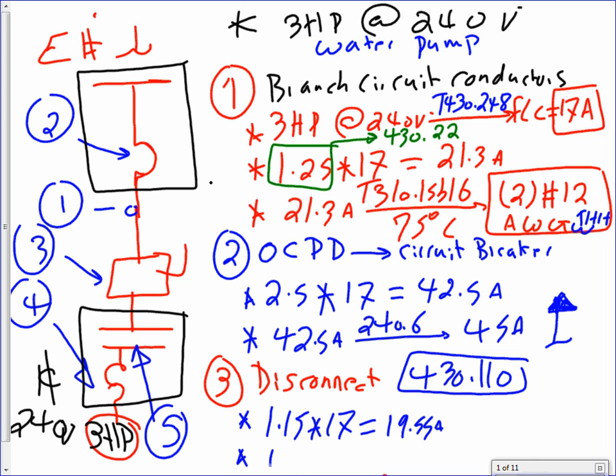If you take the 19.55 amps, you're going to take this one to the DeWalt, page 3-12. You're going to get 30 amps. Gentlemen, when you say DeWalt, page 3-12, that's what I told you. On the test, if you don't have DeWalt for the first 7 weeks, I'm okay. Next, for the commercial industrial project, you must have that one. It says sizes of disconnects. Right here, the smallest disconnect you can buy is 30 amps. Everybody understands what the DeWalt is, this book right here in front of you? So my disconnect is going to be 30 amps.